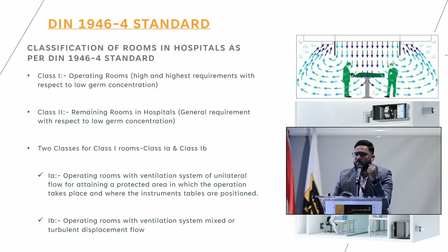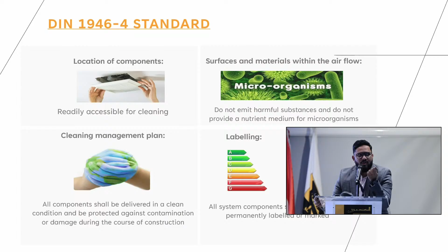Now, what the standard says about the location of components is that each component used in the air handling unit has to be easily accessible and cleanable, so there is no growth of fungi or bacteria which can carry into the airstream. It also states requirements for the surfaces and materials used in manufacturing an air handling unit which come in contact with air. For the location of components, as defined by the 1946-4 standard, everything should be easily accessible, even the cooling coil and the drain pan, so that everything in an air handling unit can be easily removed, cleaned, and accessed by the maintenance person.